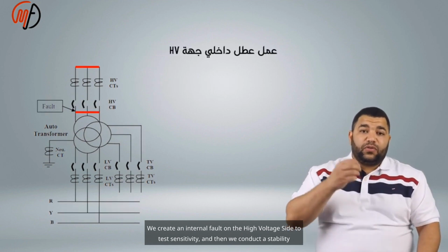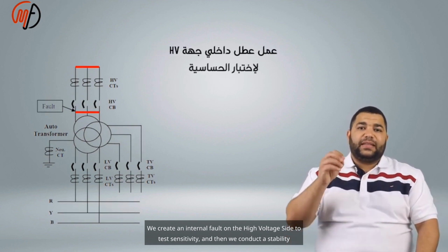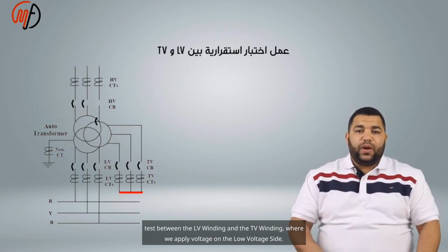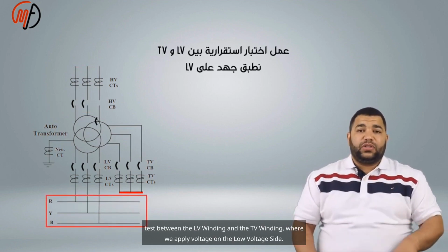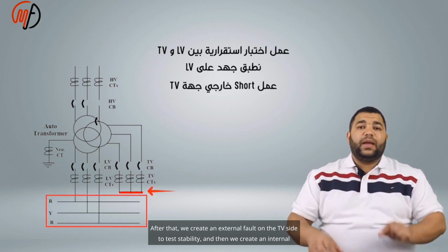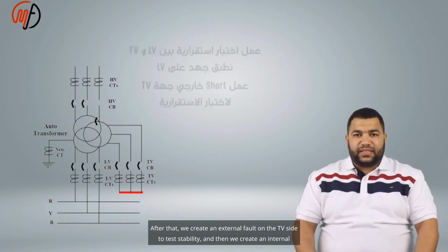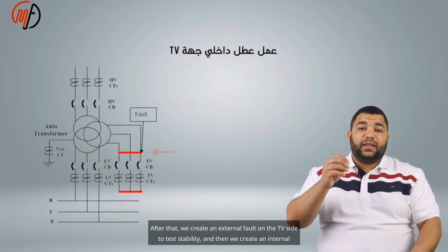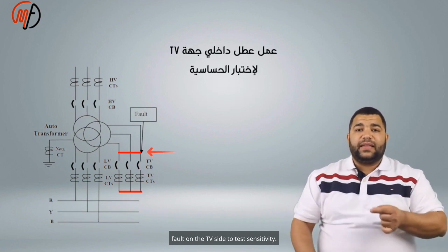We create an internal fault on the high voltage side to test sensitivity. And then we conduct a stability test between the LV winding and the TV winding, where we apply voltage on the low voltage side. After that, we create an external fault on the TV side to test stability. And then we create an internal fault on the TV side to test sensitivity.